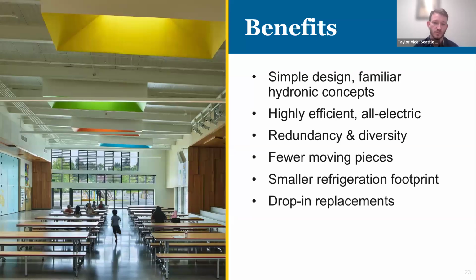The fewer machines we have, the more centralized they are, the fewer moving pieces we have to deal with—fewer pumps, fewer compressors, things like that. And that gives us a smaller refrigeration footprint, so we're doing less reporting to the EPA and replacing refrigerant less often. So we see a big benefit to those centralized type systems.